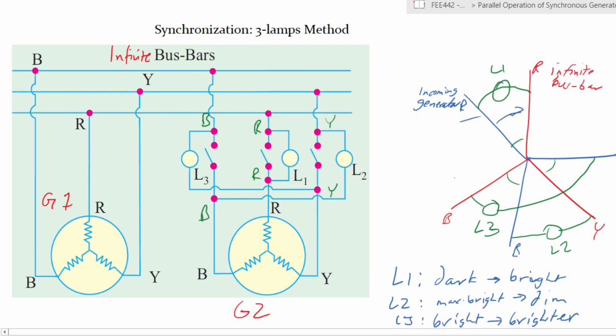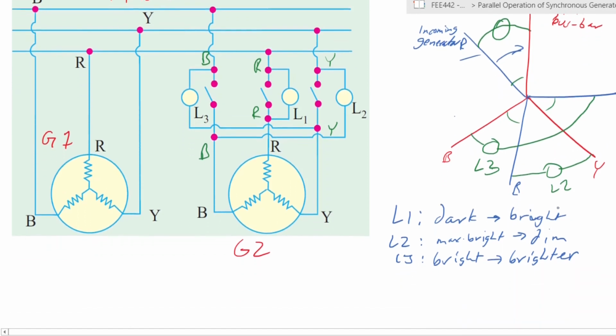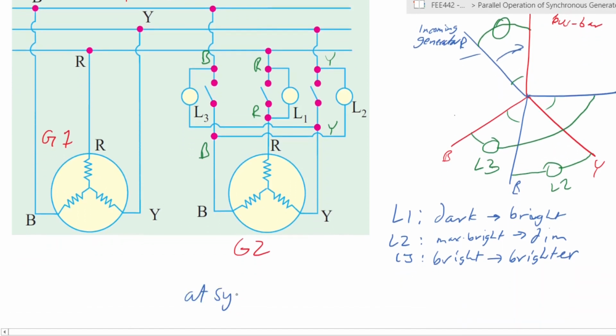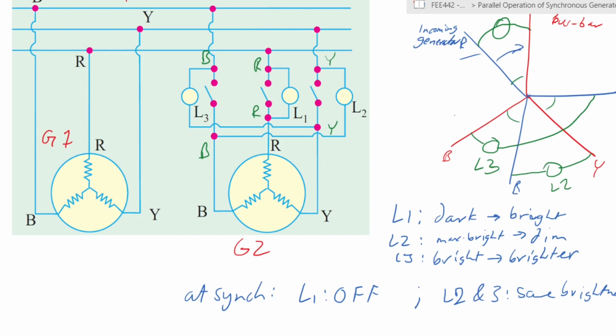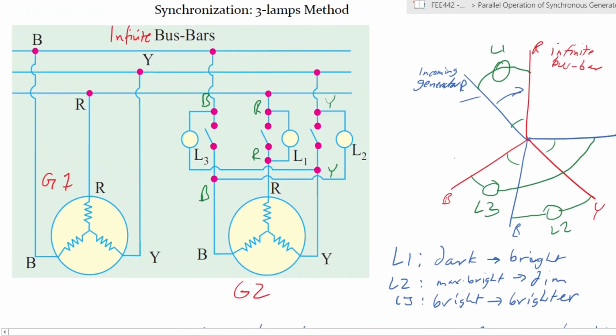And at that point, you will find that lamp number 1 will go off, and then lamps 3 and 2 will be fully bright at the same brightness. Okay, so at the moment of synchronization, lamp 1 is off, and lamps 2 and 3 are at the same brightness. Now, of course, this poses the problem of how we would be able to note that. How do we fully indicate? This was a system that was in use. It's a fairly easy system to put in place, so you would run into it in some places.